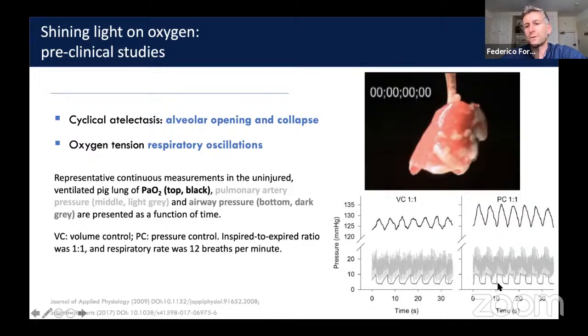And you see that instead of a constant flow, there's a very rapid flow increase at the beginning of inspiration, and then a pressure is maintained for the duration of inspiration, and then it is released as is done during expiration. So at this stage, we were able to essentially demonstrate that the sensor responded rapidly, was able to track ventilatory oscillations in animals, and didn't clot. So we thought that we had sufficient evidence to move on to patient studies.